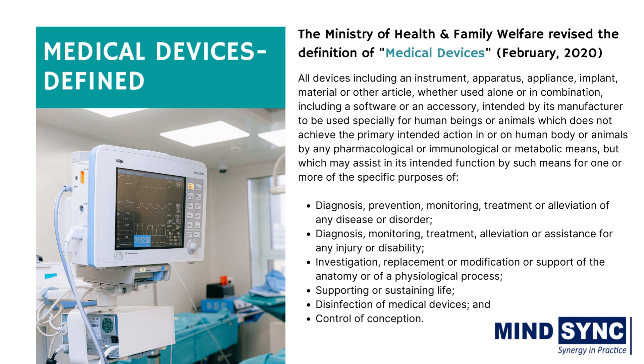Moving forward, let us now know the definition of medical devices. According to a notification issued on February 2020, medical devices that meet the following definition will be regulated as Drugs under the Drugs and Cosmetic Act and Medical Devices Rules. All devices including an instrument, apparatus, appliance, implant, material or other article, whether used alone or in combination, including software or an accessory, intended by its manufacturer to be used specially for human beings or animals, which does not achieve the primary intended action in or on human body or animals by any pharmacological, immunological, or metabolic means, but which may assist in its intended function by such means for one or more specific purposes like diagnosis, prevention, monitoring, treatment or alleviation of any disease or disorder.